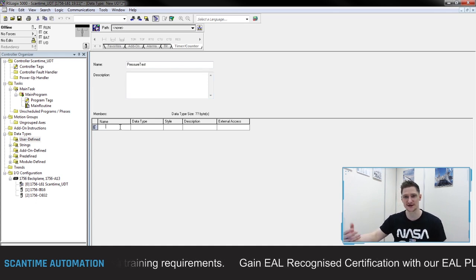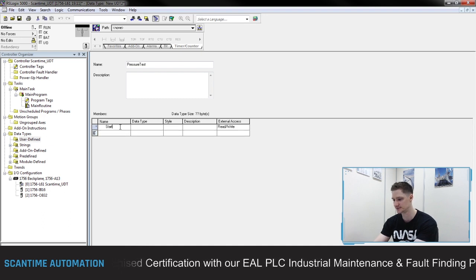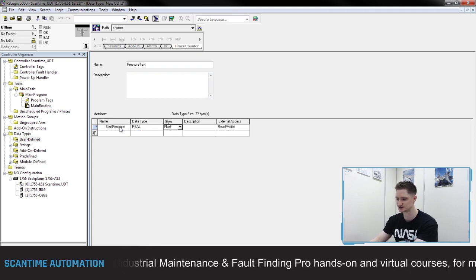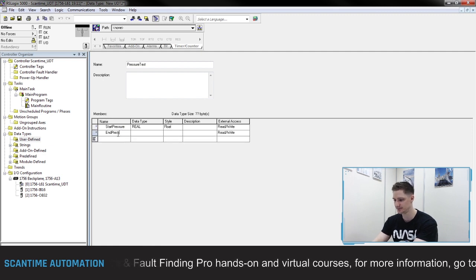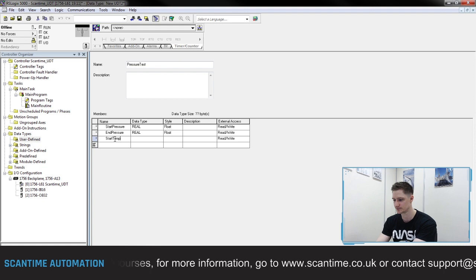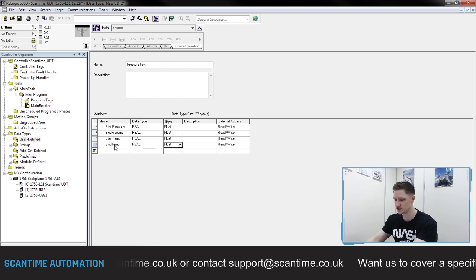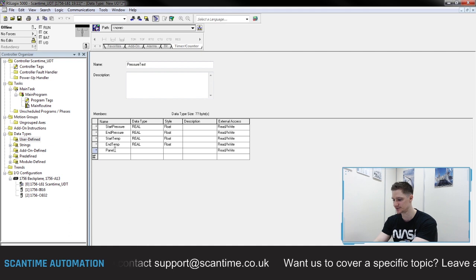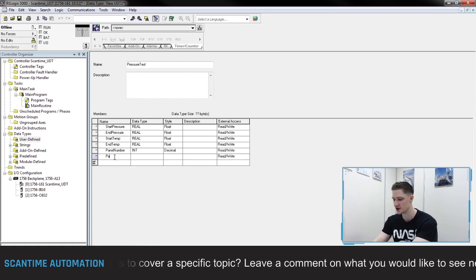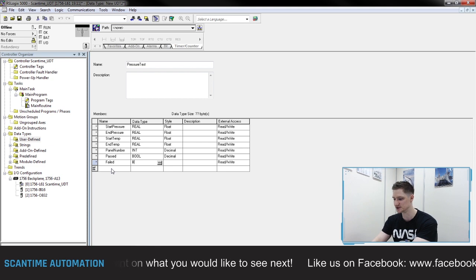Where we see the name, this is where we enter our data fields. In my pressure test I'm going to be collecting: start pressure — data type real (decimal point); end pressure — also a real value; start temperature — real value; end temperature — real value; panel number — integer; and also the pass or failed signal. 'Pass' is going to be a boolean — on or off — and 'failed' is going to be a boolean as well.